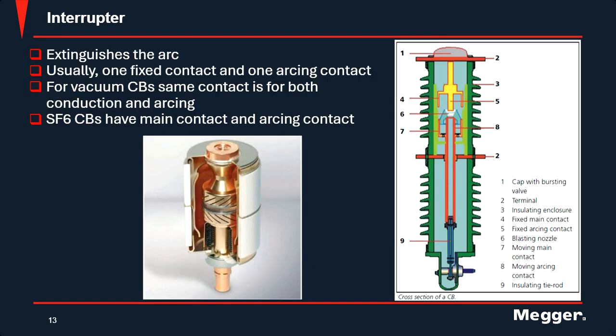All right, so you heard me talk about interrupters earlier. That's what's inside of the breaker, per phase. The interrupter is meant to extinguish the arc while doing an open or close command. The main contact in the circuit breaker is the current carrying element between the stationary and the moving part of the interrupter. Depending on the classification, this is an interrupter for a vacuum breaker over to the left. Generally for a vacuum breaker, you don't have that arcing contact, just the main contact. And then you also have an SF6 interrupter on the right. It has a primary contact and a secondary contact. Like I said before, the primary contact is the main element that carries the current, and the arcing contact is just there to help extinguish the arc, either during a close command or opening command.